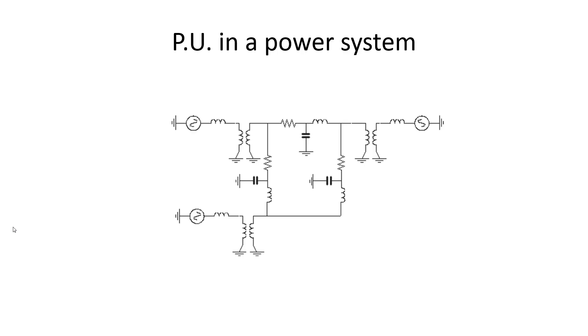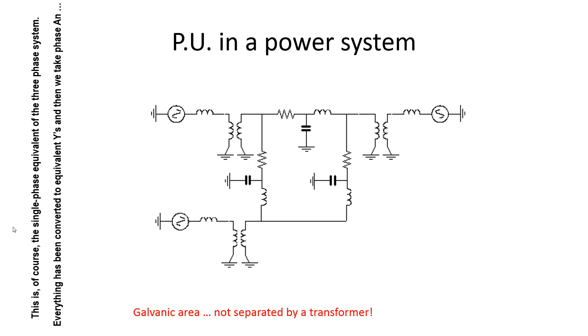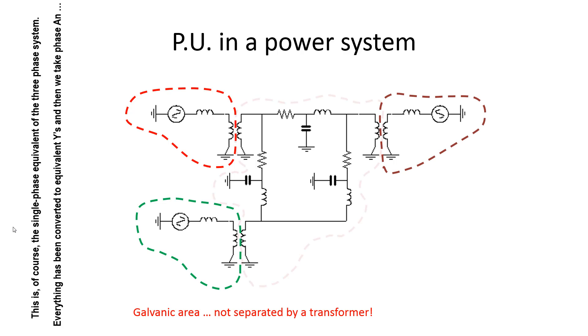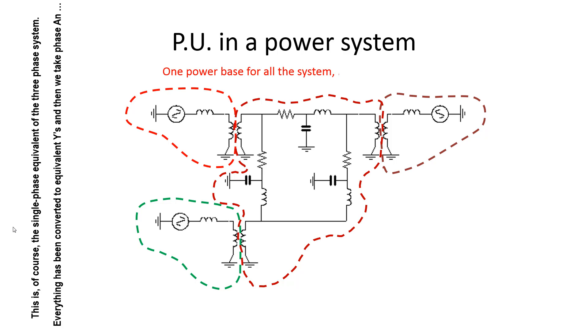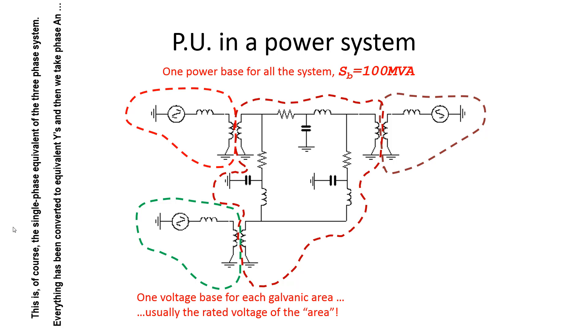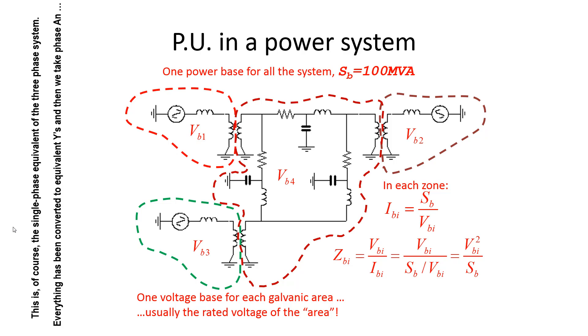What about a power system? We begin by defining what is a galvanic area: it is a part of the circuit not separated by the magnetic field of a transformer. In this circuit, there are four galvanic areas. We will use one power base for all the system — in America it is customary to use 100 MVA as the base for power. For each galvanic area, we choose the rated volts as the base voltage: VB1, VB2, VB3, and VB4. Then we compute the rated current and base ohms in each zone.